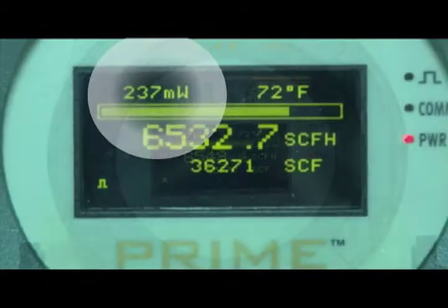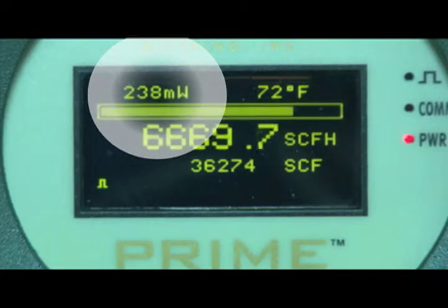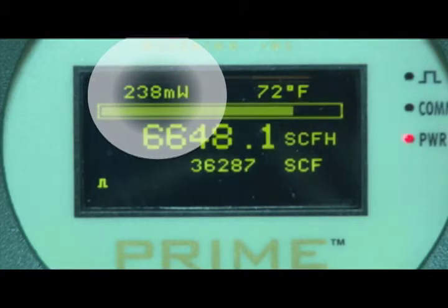In addition, there are readings in milliwatts in the top left corner, representing the raw calibration output. It can be used for diagnostics, and most importantly, to verify the meter's calibration during the in-situ calibration procedure.